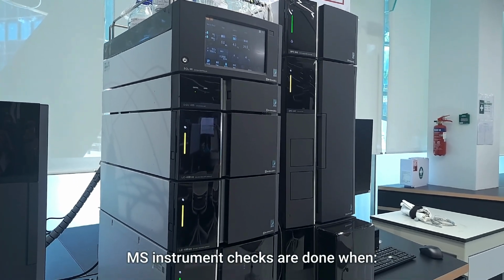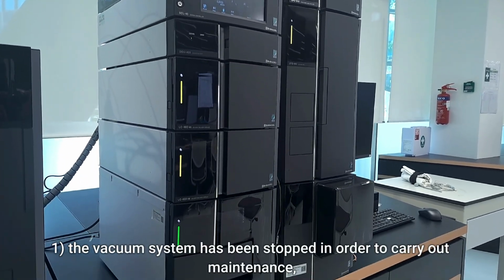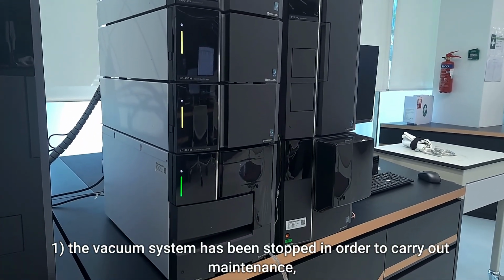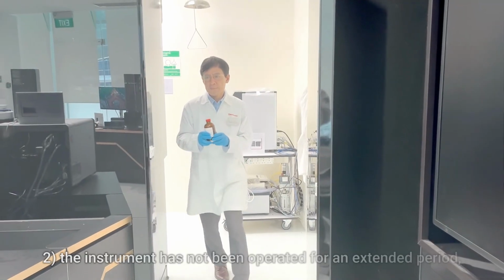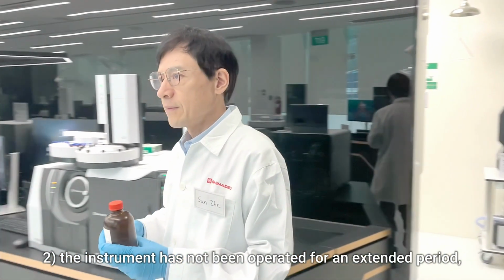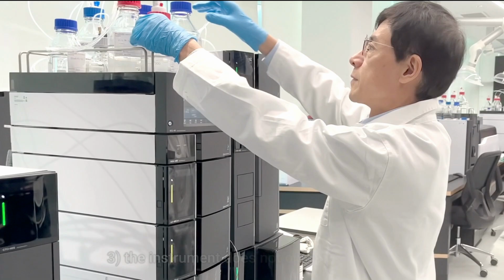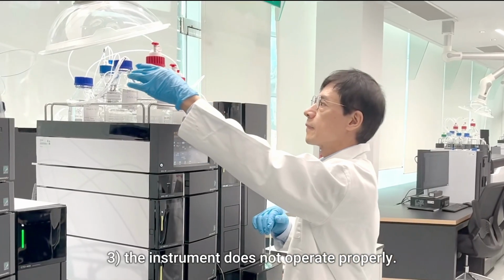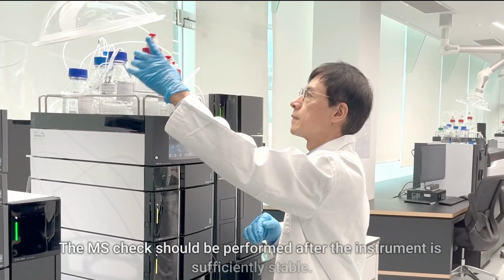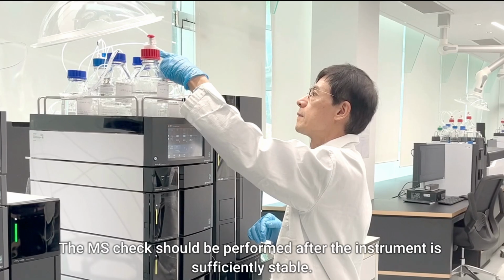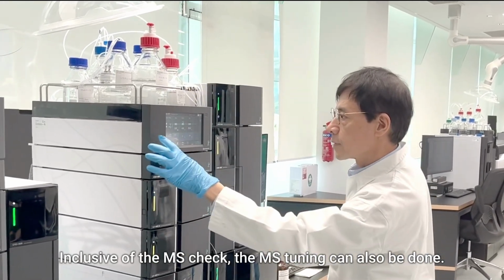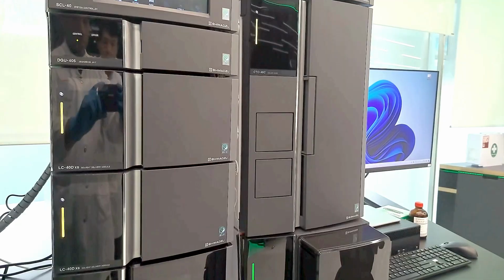MS instrument checks are done when 1. The vacuum system has been stopped in order to carry out maintenance. 2. The instrument has not been operated for an extended period. Or 3. The instrument does not operate properly. The MS check should be performed after the instrument is sufficiently stable. Inclusive of the MS check, the MS tuning can also be done.